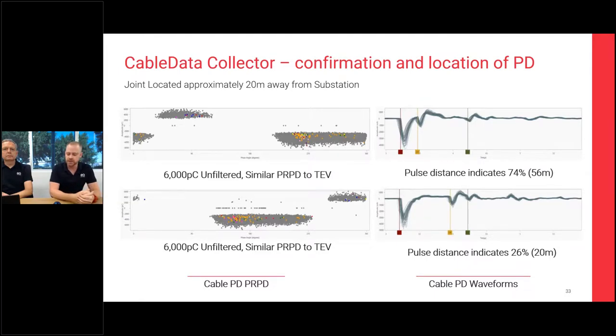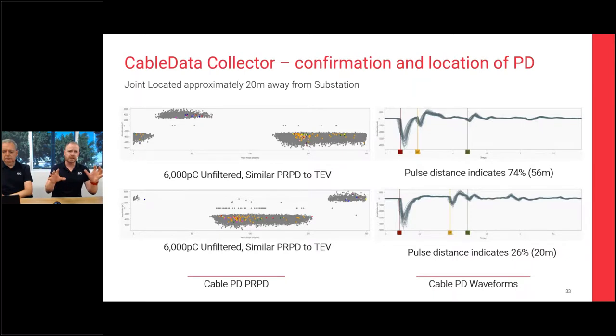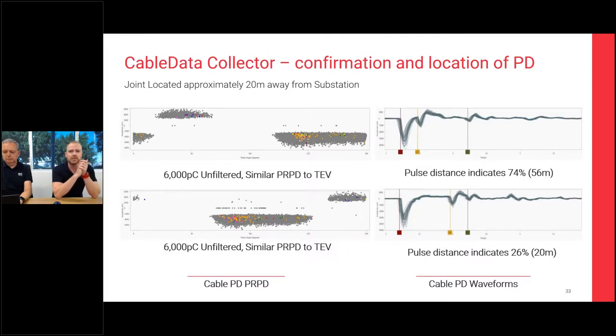Testing from the other substation showed a similar phase-resolved pattern and indicated 20 meters from that substation back the other way — a good indication of PD signals emanating from something there. Looking up the cable history and data, a joint was located around 20 meters away from substation B. So the recommendation was to investigate and consider what to do about that joint. The amplitude level was 6,000 picocoulombs at unfiltered data. Relating that back to the thresholds table, 6,000 pC is in the red level — a defect with a high priority. This demonstrated the use of multiple instruments and knowledge of an interconnected network: when you have signals, you need to be able to track them down and figure out where they're coming from.